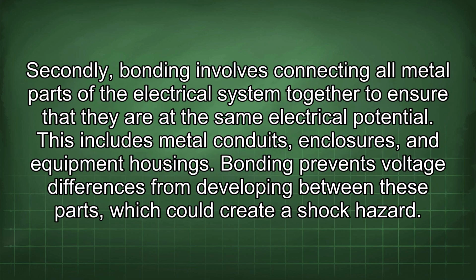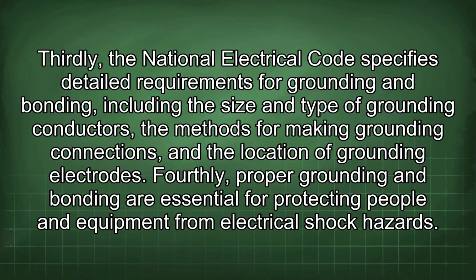Secondly, bonding involves connecting all metal parts of the electrical system together to ensure that they are at the same electrical potential. This includes metal conduits, enclosures, and equipment housings. Bonding prevents voltage differences from developing between these parts, which could create a shock hazard. Thirdly, the National Electrical Code specifies detailed requirements for grounding and bonding, including the size and type of grounding conductors, the methods for making grounding connections, and the location of grounding electrodes.